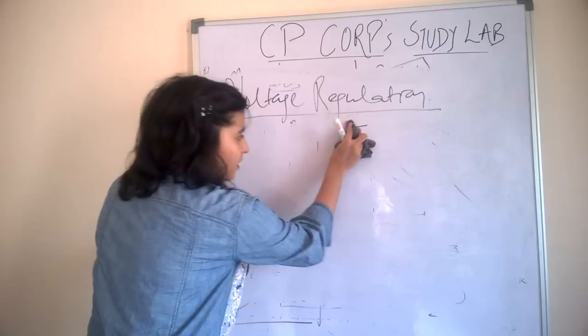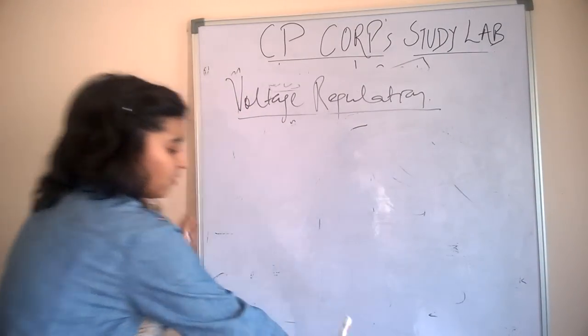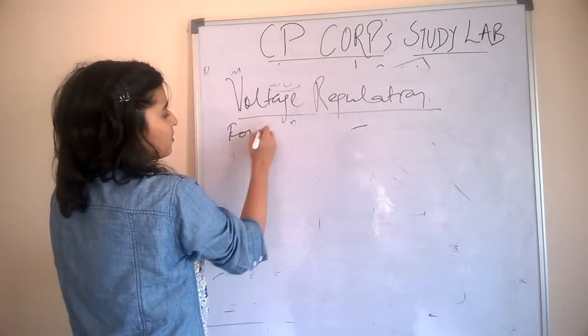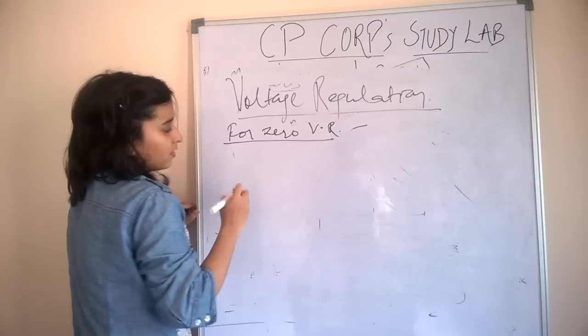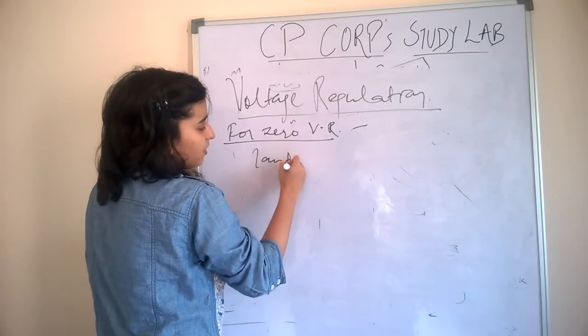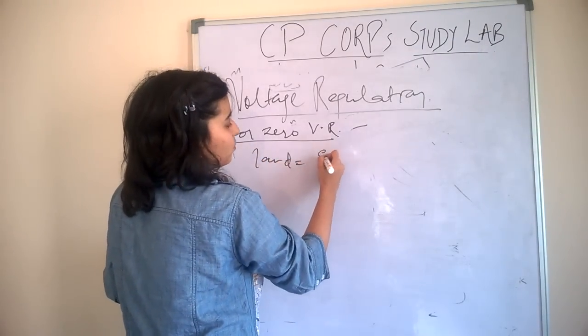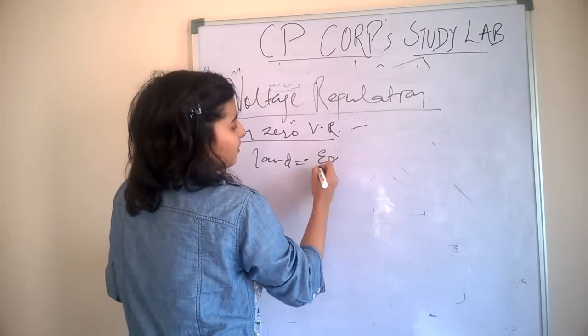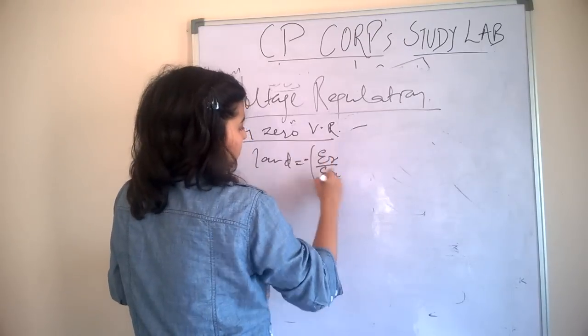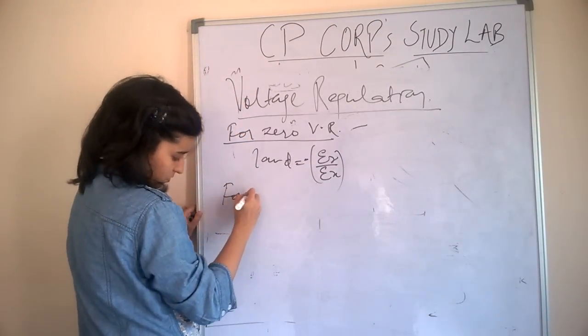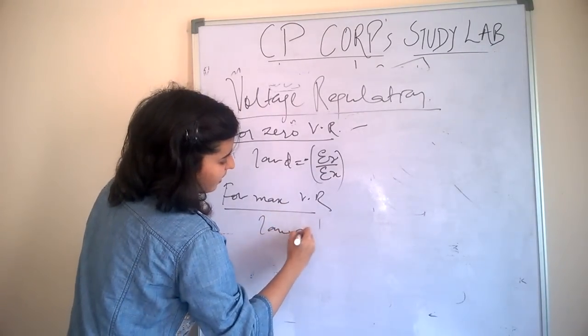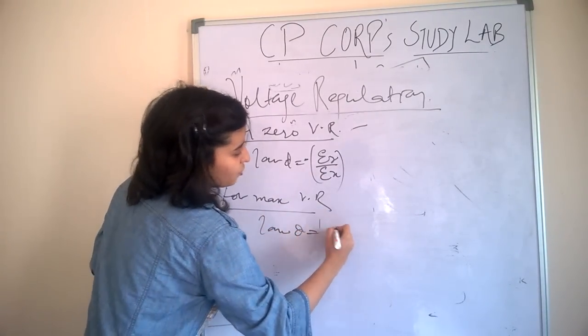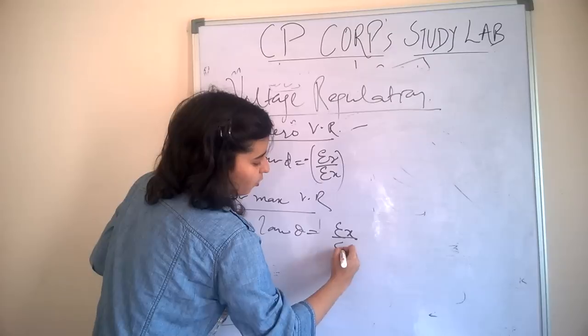For zero voltage regulation, tan θ should be equal to -R/X. And for maximum voltage regulation, tan θ should be X/R.